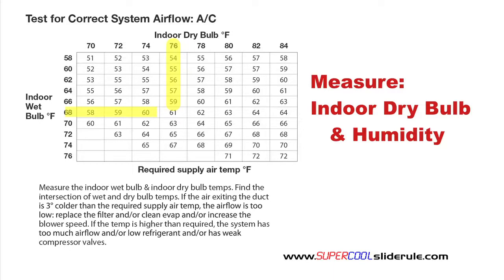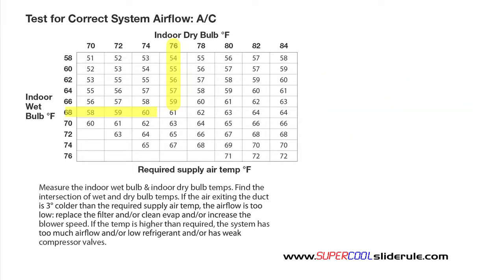Find the indoor dry bulb temperature and the indoor wet bulb temperature. Find where these two correspond. At the intersection of those is the required supply air temperature.